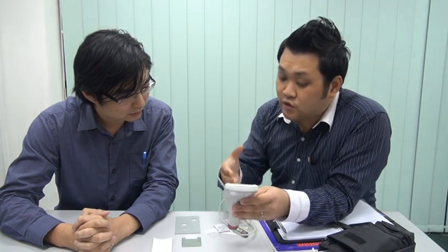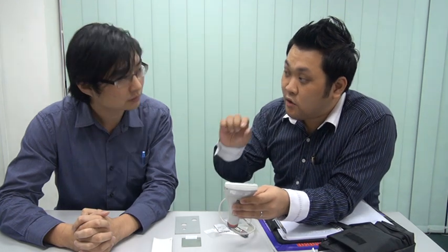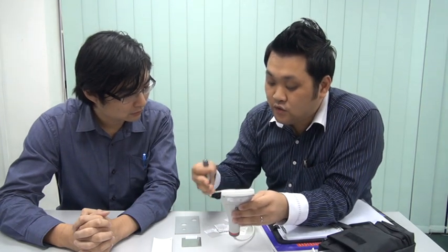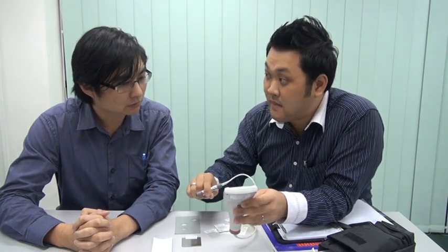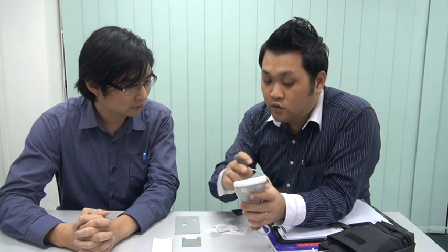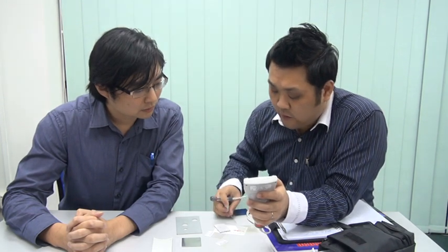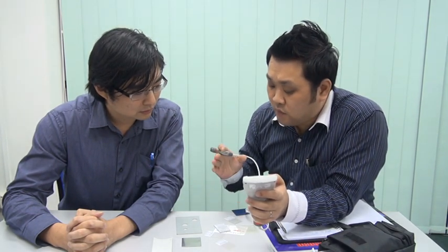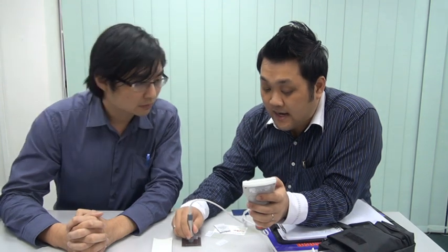No matter how intelligent this gauge is, you need to let the gauge know what thickness the foil you are measuring right now is. So we are letting the gauge know that we are measuring 63.6 micron. Then it will ask you to put the sensor on the second calibration. Because I don't have one nearest to your thickness, I will use a higher one compared to the previous one. So it's 900.